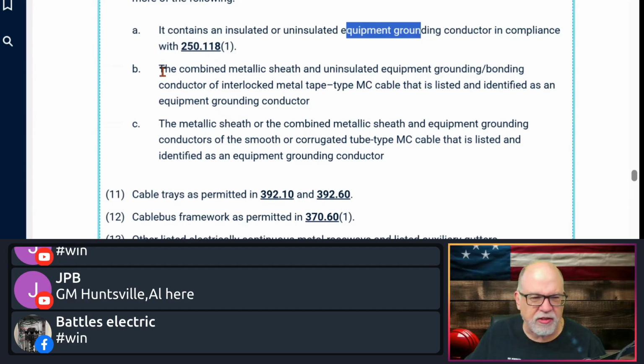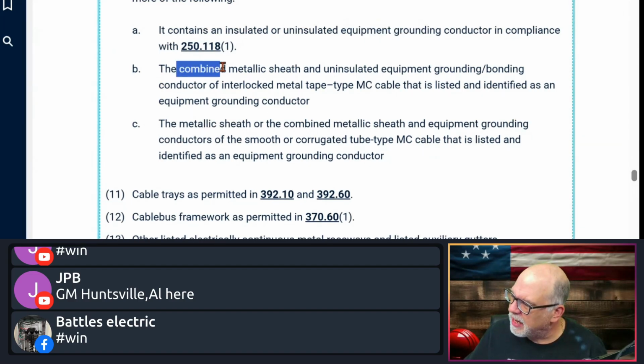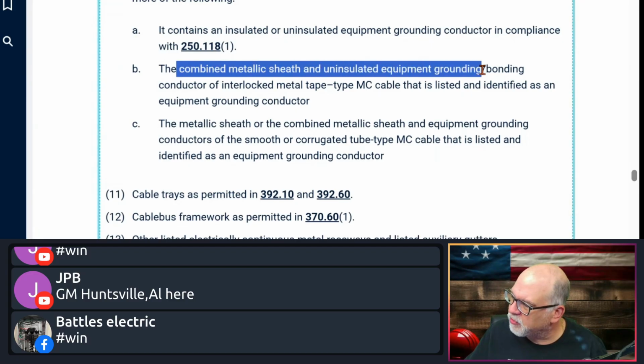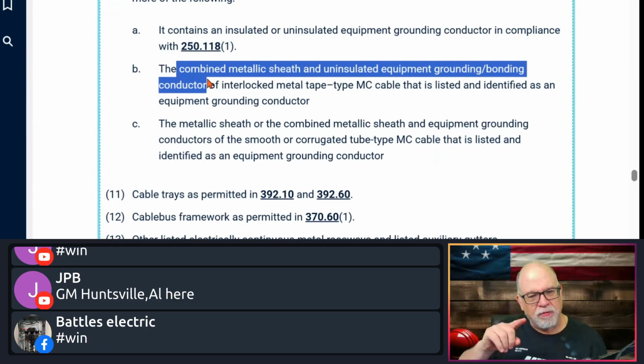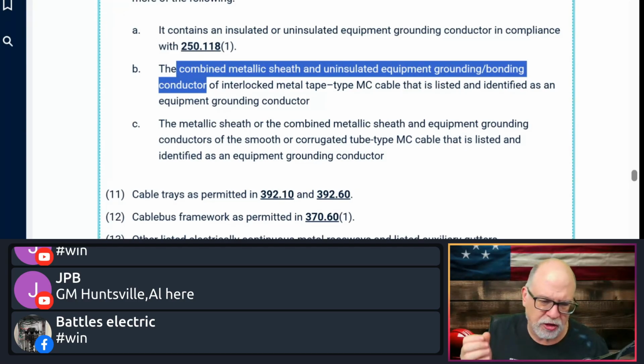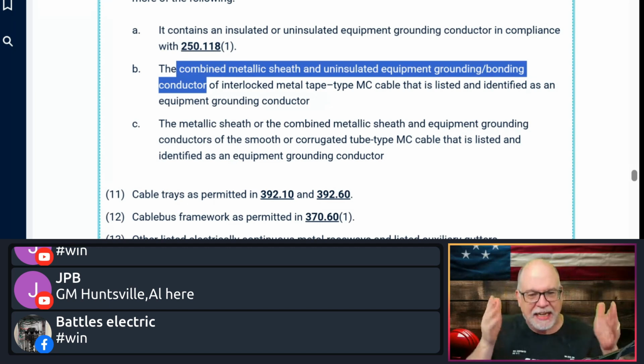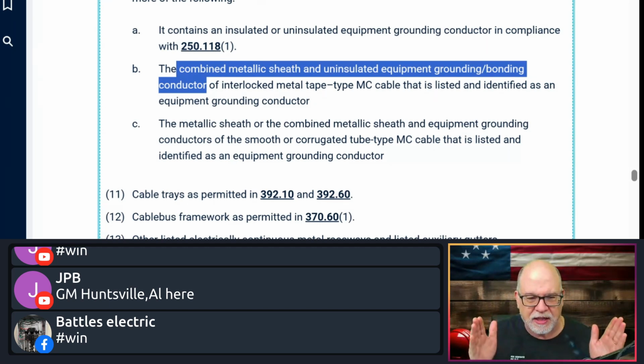The next one, this is where you learn stuff. Here it says, a combined metal sheathing and uninsulated equipment grounding/bonding conductor. That's what you folks see in that MCAP or that smart ground products that you can buy. That aluminum conductor. And people ask me, if I had a dollar for every time somebody asked me about that aluminum conductor, they go, do I bring that into the box? What do I do with it? You cut it off at the end. You don't need it anymore. It was only there to make intimate contact with the convolutions. Okay, that's a grounding/bonding conductor.